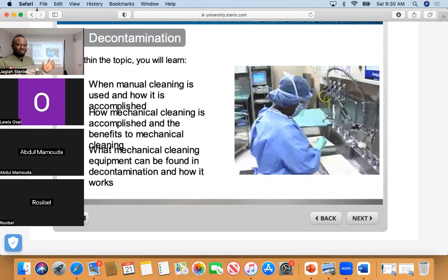But anything metal, from now on, you have to know how to clean. Well, you know how, I'm going to show you, but anything metal, you have to understand, you can soak it in water. Does it make sense? Mm-hmm. You can soak, brush, clean, rinse. Anything metal can go in any form of mechanical washer. So after manual cleaning, it goes on to ultrasonic for 15 minutes. If there is a lot of blood, ultrasonic will help break it down further before you put them onto the automated washer disinfector.